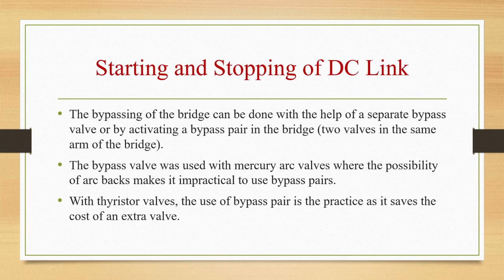The bypass valve was used with mercury arc valves, where the possibility of arc backs makes it impractical to use bypass pairs. So along with the mercury arc valve, we used a bypass valve in the earlier days, because an arc back would occur in the bypass pairs. With thyristor valves, the use of a bypass pair is practical as it saves the cost of an extra valve.